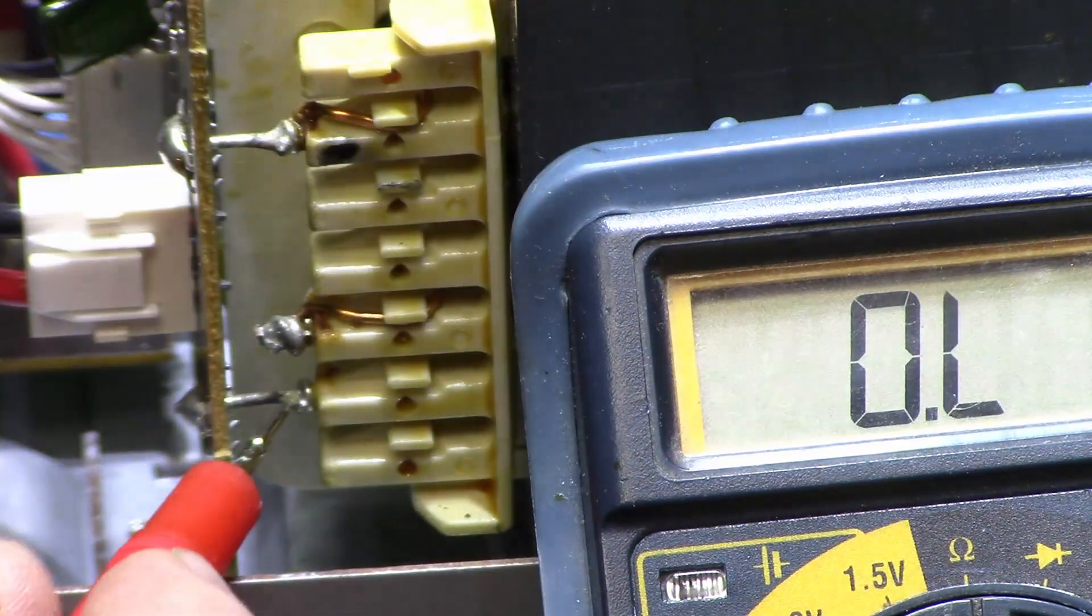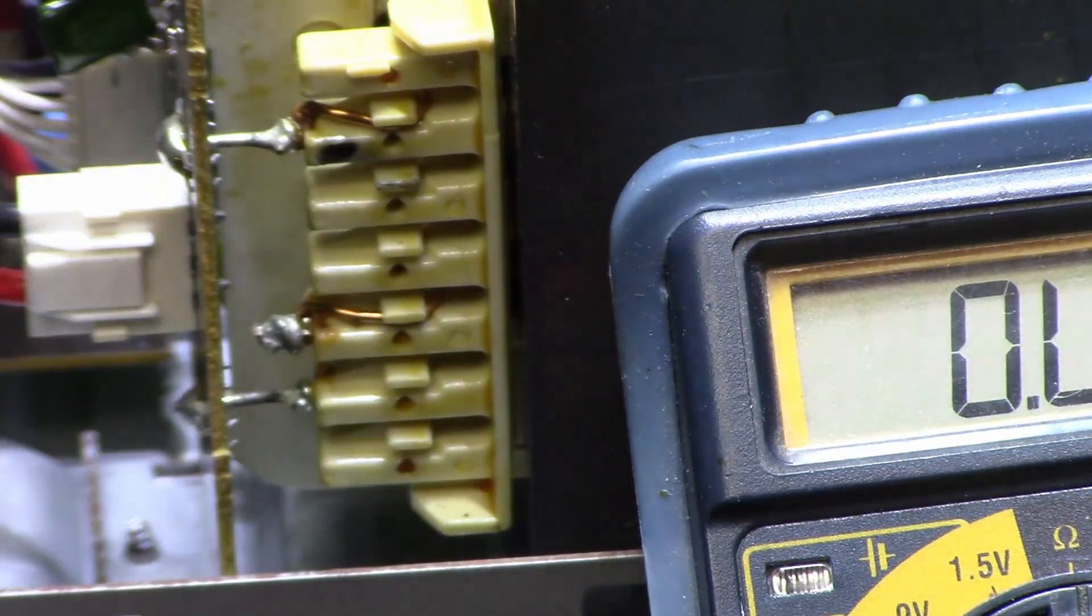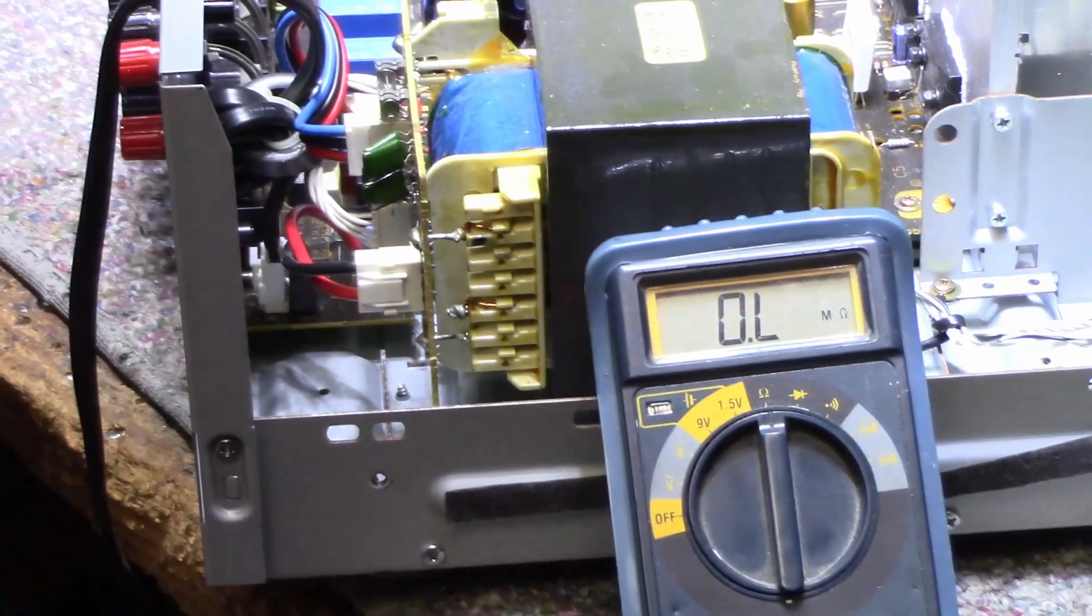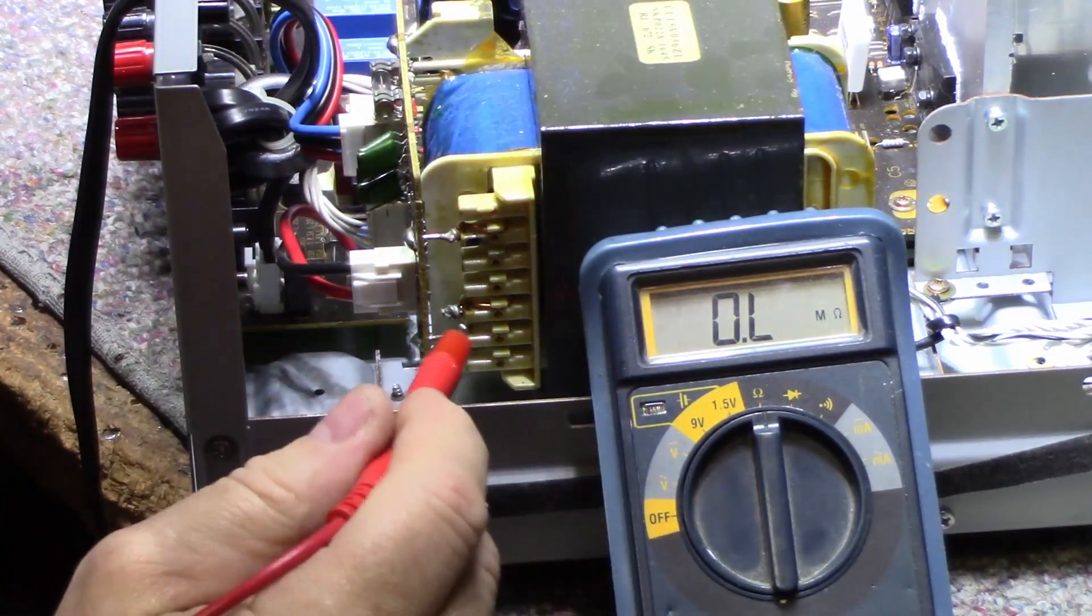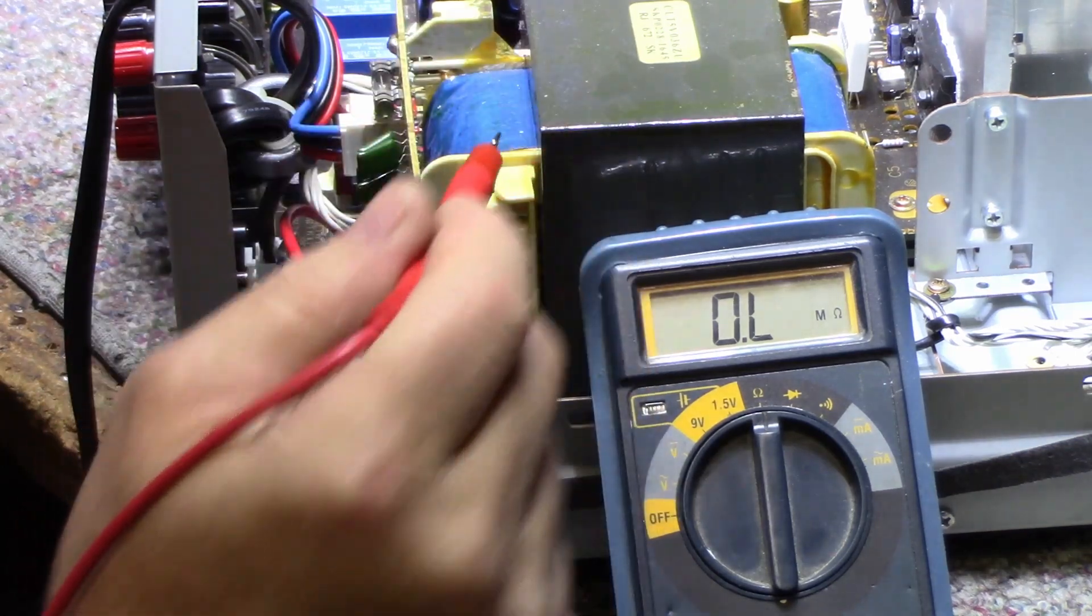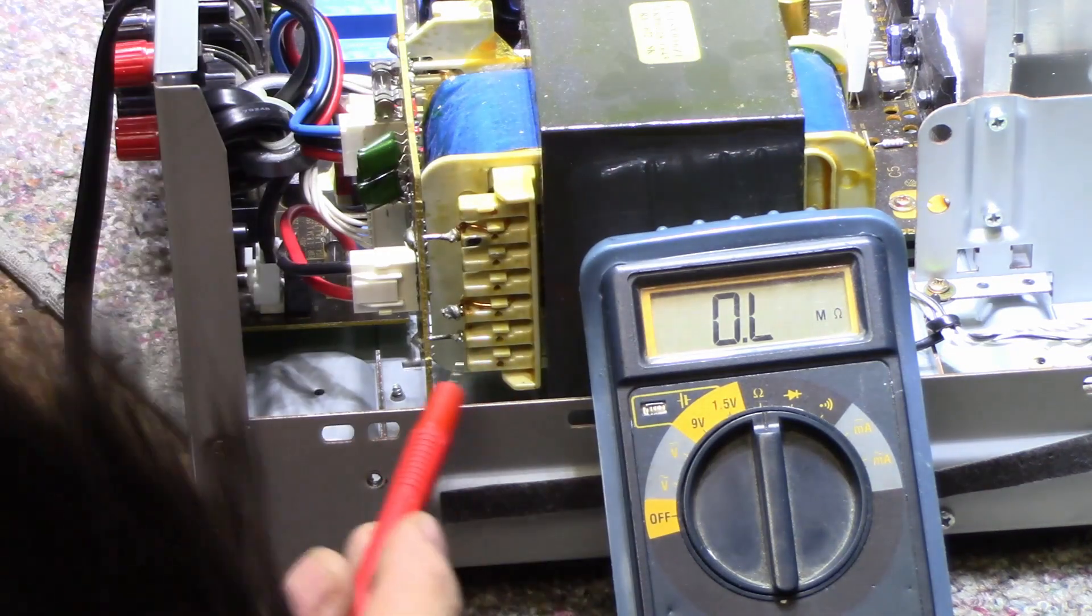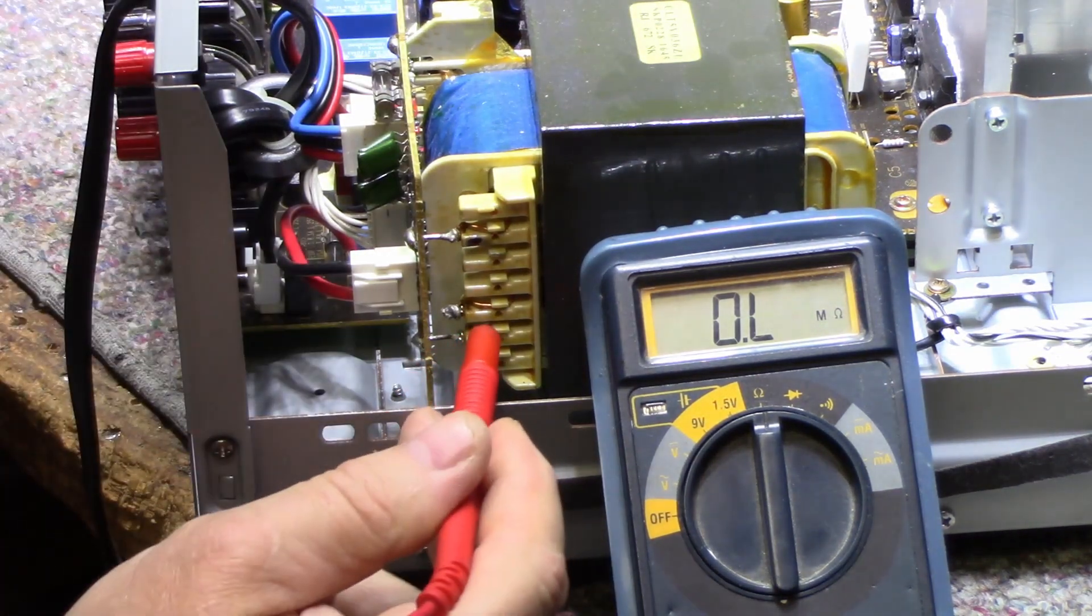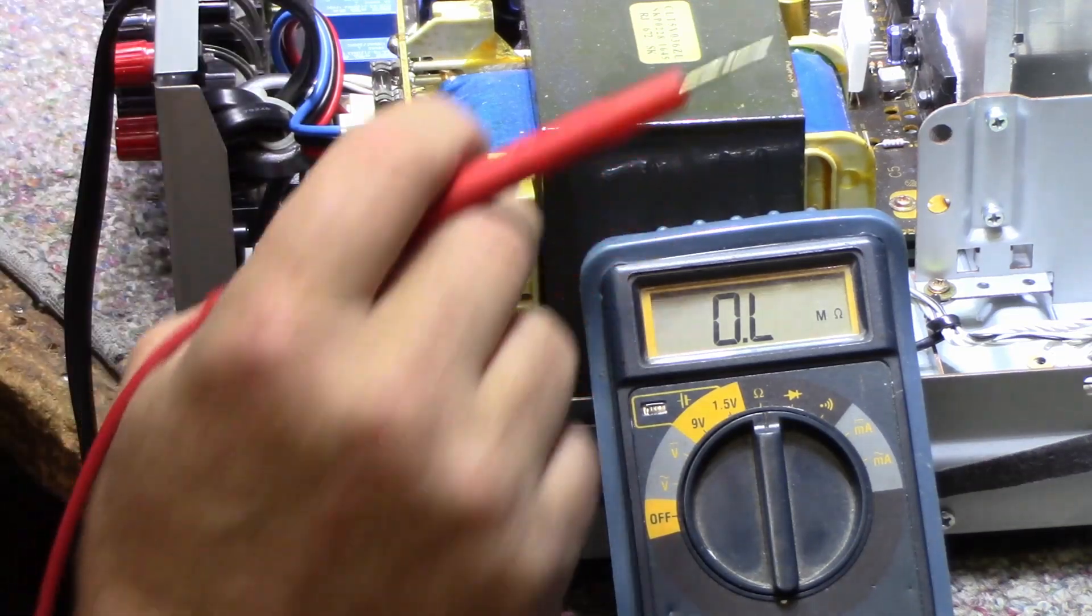So check and see if this fuse is open, which I suspect it would be. If you look down from the top, you can see the wires for the fuse going in. They go between the primary winding and the secondary winding. There's a thermal fuse in there.